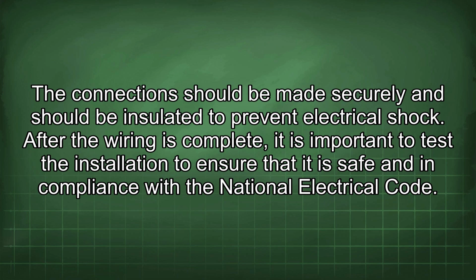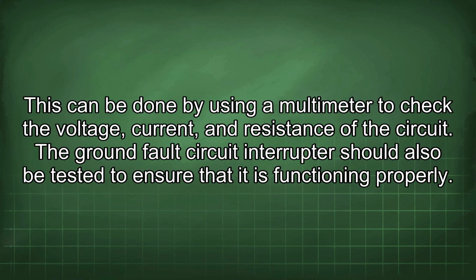After the wiring is complete, it is important to test the installation to ensure that it is safe and in compliance with the National Electrical Code. This can be done by using a multimeter to check the voltage, current, and resistance of the circuit. The ground fault circuit interrupter should also be tested to ensure that it is functioning properly.